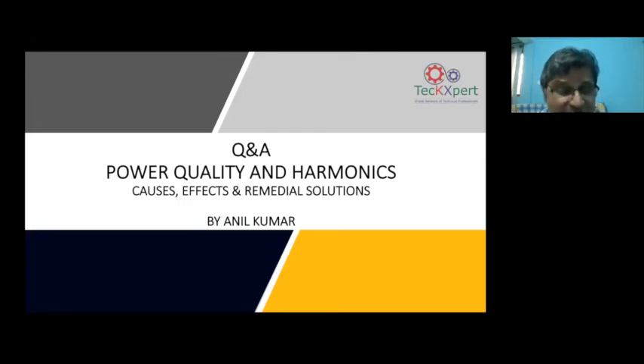We can even catch the manufacturer of the contactor and tell them, look, you said this is the resistance you have provided and the switching current is only so much, and now the resistance or the contactor is failing. Okay. With the proof we can fight.